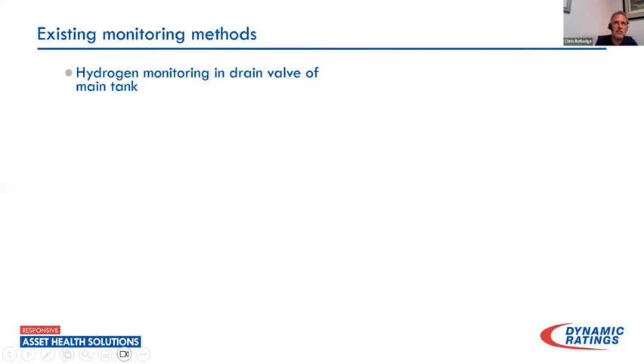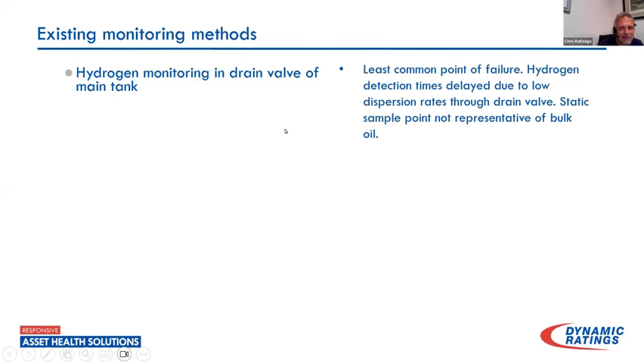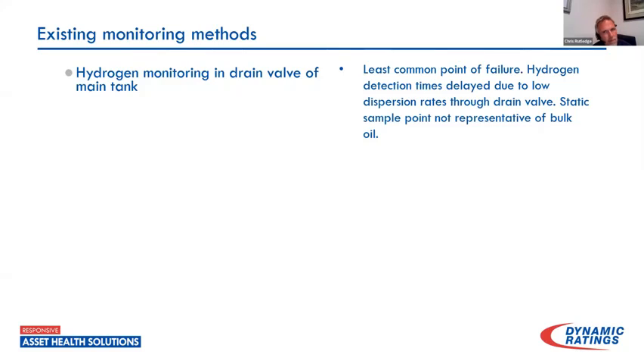When I went to my vendors, I said I need something to look at this. What came back to me was hydrogen monitoring in the drain valve of the main tank. But again, main tank is not really where I was seeing them fail. I've also done quite a bit of experimentation on how quickly hydrogen migrates through oil to drain valves and how reliable that is. When you're at that main drain valve, you're really measuring from a static point — I've had to drain two or three gallons of water off before pulling a sample. It's a convenient place, but maybe not the most effective.